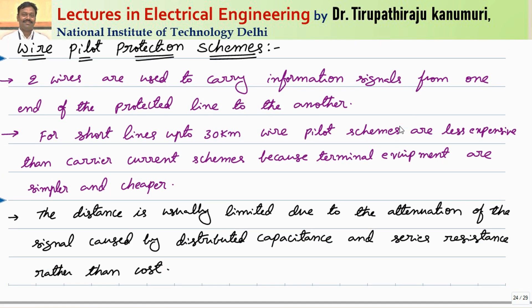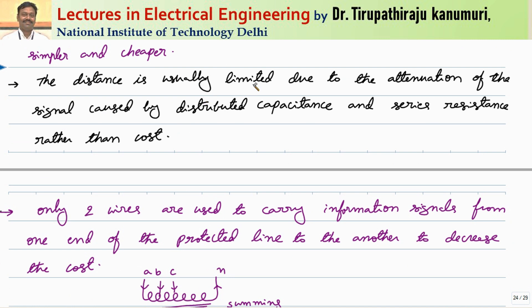For pilot wire protection schemes with three-phase systems, single phase requires two wires, but three-phase requires at least four wires — three for the phases and one for the neutral. Keeping four wires drastically increases cost. Instead, we use a scheme where only two wires carry the information signals from one end of the protected line to the other. For short lengths up to 30 kilometers, wire pilot schemes are less expensive than carrier current schemes because the terminal equipment is simpler and cheaper — direct cable only is used.